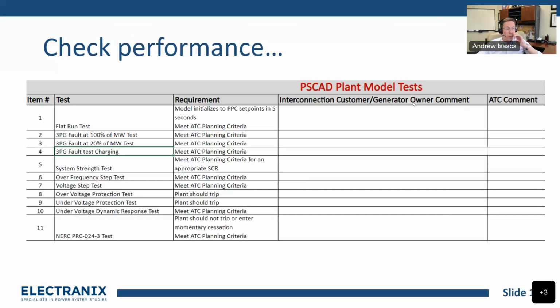And finally, you can do some performance checks. This is a fairly short, simple list of tests, and they've got a document that prescribes the pass-fail criteria for these. You do a flat run test, a phase to ground fault, a 3-line to ground fault at 100%, a 3-line to ground fault at low power. But if there's a battery in the plant and it's charging, you can look at that too. They also do a system strength check over frequency, voltage step, overvoltage, undervoltage, etc.